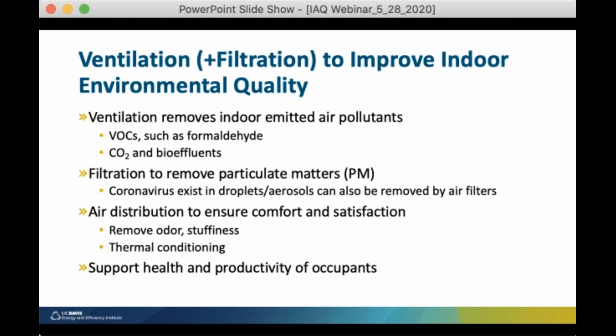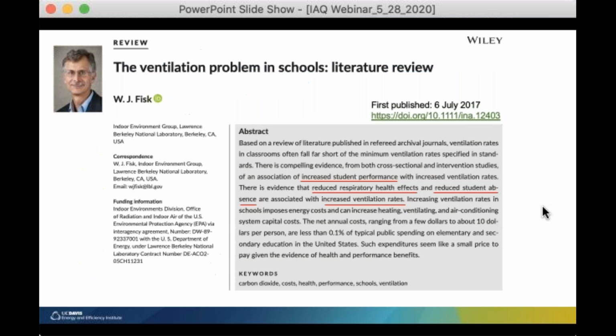Now, as coronavirus exists in droplets and aerosols, some of them are in the size range that can be removed by air filters. In addition to the amount of outside air, a well-designed air distribution system is also important to ensure thermal comfort of occupants. So people want fresh air, and they also want it to be not too hot, not too cold, not too noisy, and they don't want a whole bunch of air dumping on them all at once.